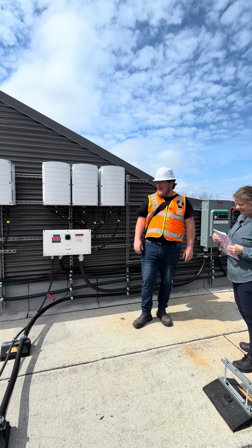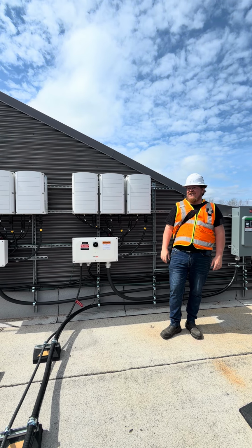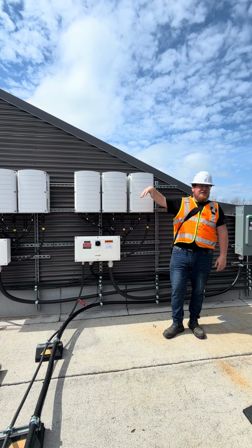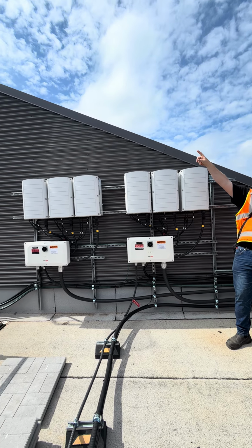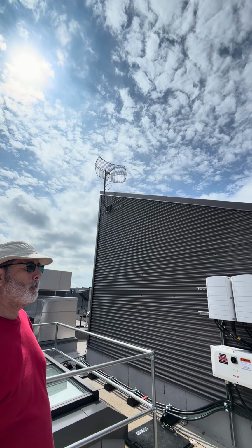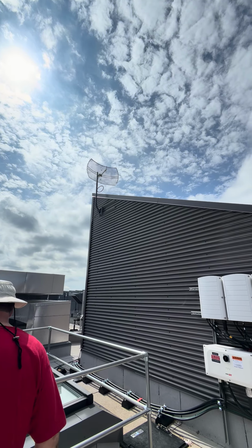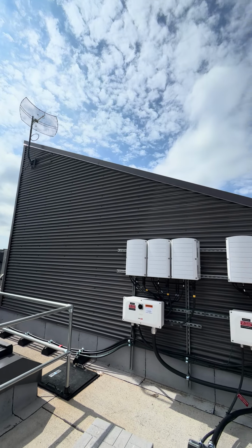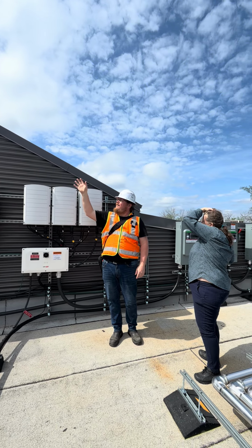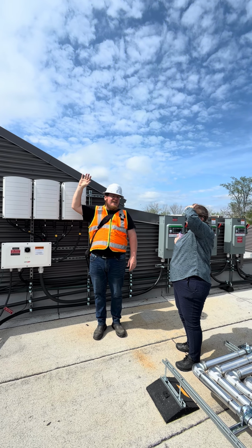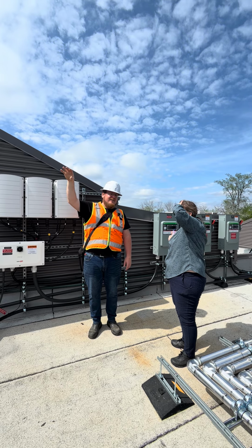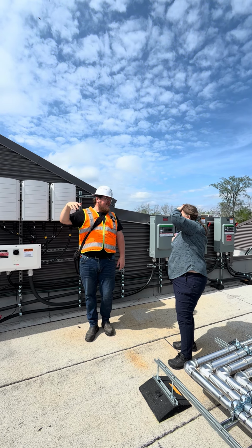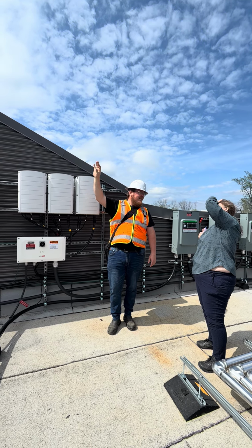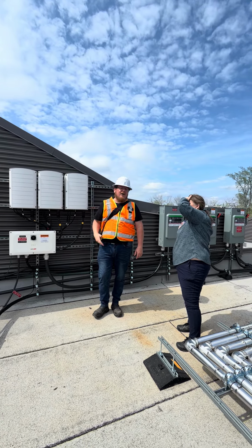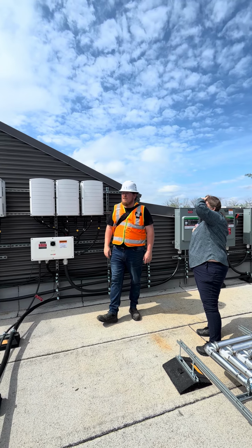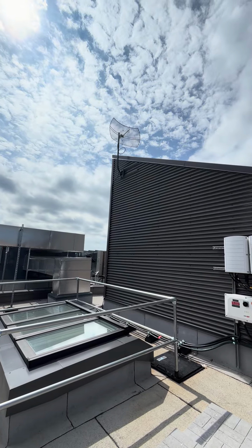Okay, any other questions about this? So the other thing we have here, I picked this one strategically, is that antenna. That antenna is what's called the transfer trip to Hydro One. It communicates line of sight to the Marysville substation. You shouldn't have to do anything with it, shouldn't be any maintenance. If there's some big windstorm and it gets knocked, your system will get disconnected because as soon as it loses the signal, it'll isolate. At that point, it's time to call Hydro One and call a service tech. And if that goes, that loses their control over the system, right?